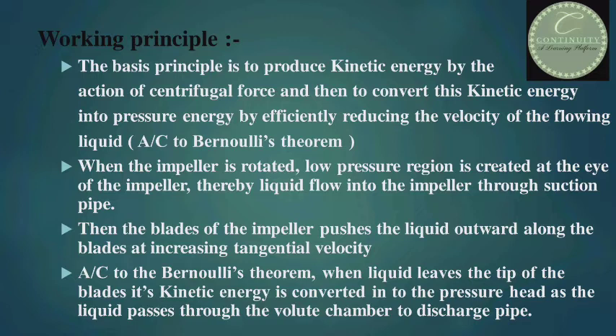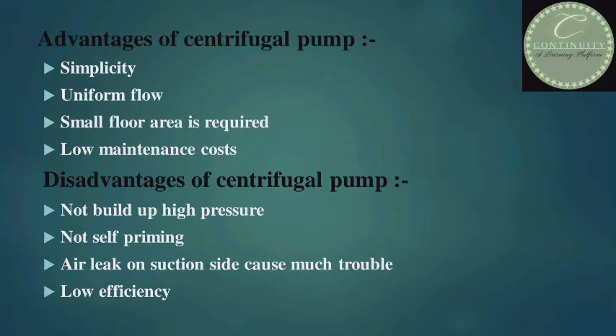Due to the low pressure at the eye, liquid flows into the impeller through the suction pipe. The blades of the impeller then push the liquid outward along the blades at increasing tangential velocity. According to Bernoulli's theorem, when the liquid leaves the tip of the blades, its kinetic energy is converted into pressure head as the liquid passes through the volute chamber to the discharge pipe.